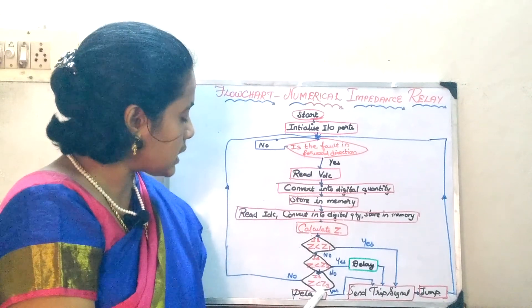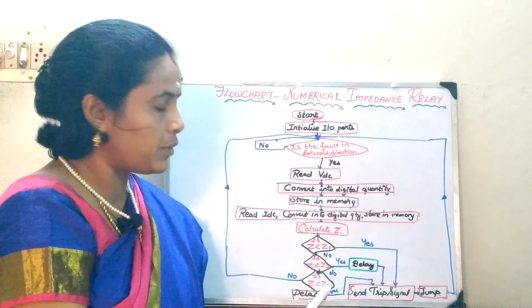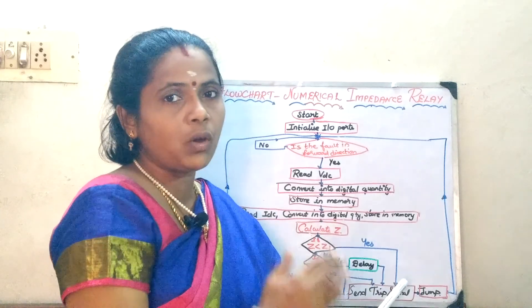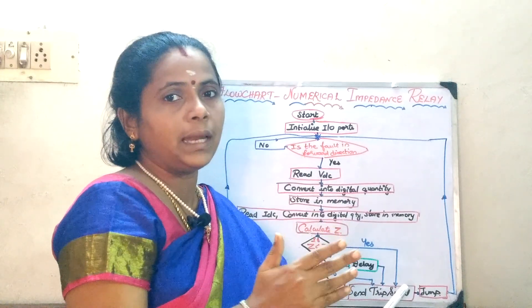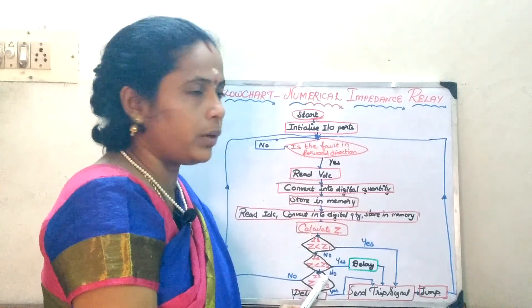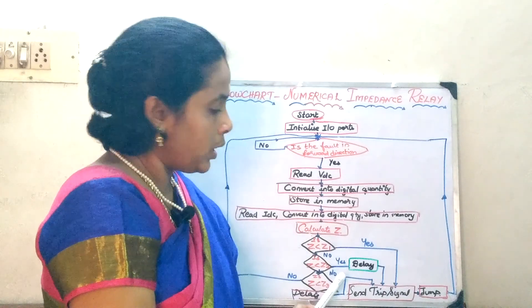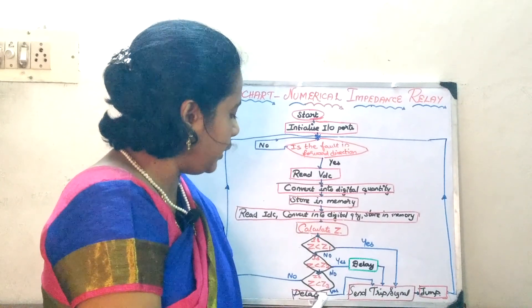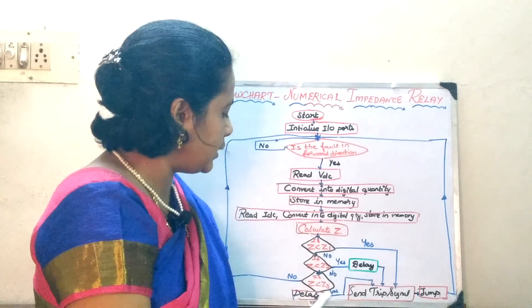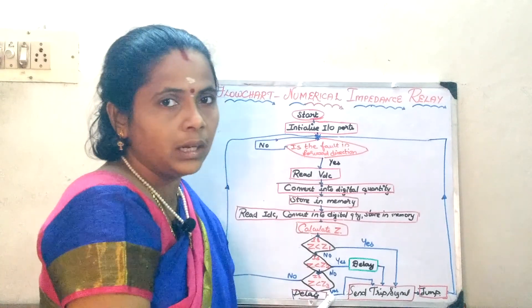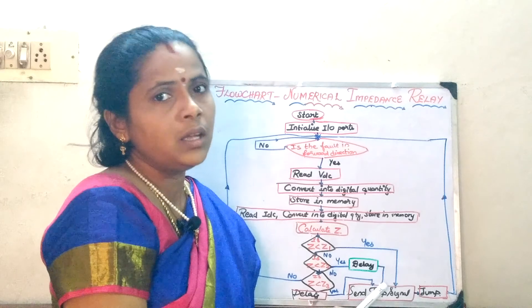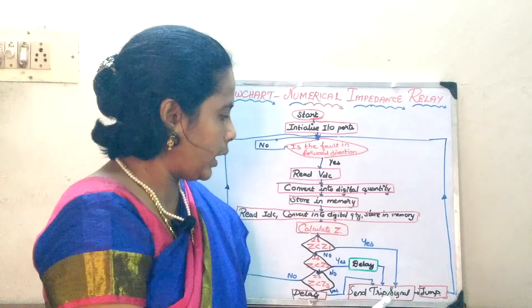In the case when Z is less than Z3, it is going to be the backup protection for the second part of the line and for the adjacent line — this will act as third zone protection. In this case, after a predetermined delay greater than the Zone 2 delay, the trip signal will be sent to the circuit breaker.